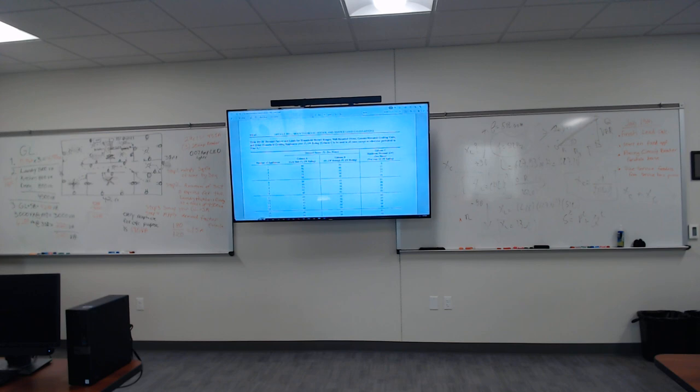This is the table right here, fellas. All right. So this right here is a demand factor. Remember, when you hear the word demand factor, that basically means how much is being utilized? Is it being utilized to its full capacity? No, not necessarily, right? You're not gonna have all four electrical burners on and the oven on at the same time at the highest peak. That's basically using it 100%. You're probably gonna be using one burner with the oven on, unless you're doing things different. But this is a demand factor, right?